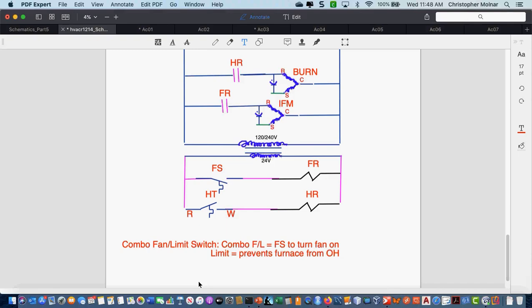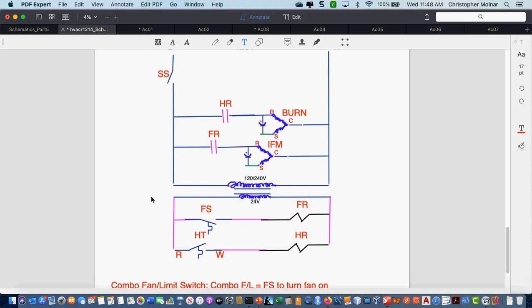So, blower motor not working. Now, if I have a limit switch that's designed to turn the furnace off if it overheats, where am I going to put it? Where in my circuit am I going to put it? Before the motor? So you're thinking between the HR and R? Or between line and HR? Between line and HR. Okay, that is valid. I could put my limit switch in right there.